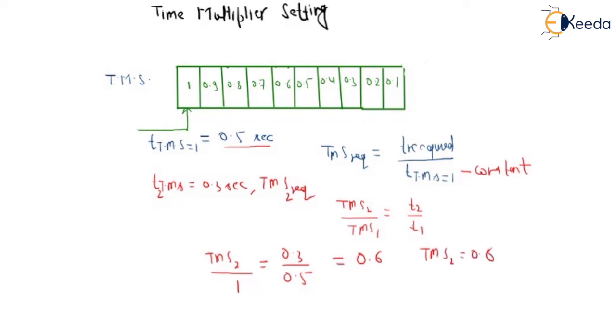If we want to operate our relay at 0.3 seconds, then we should have set this to 0.6. Means we have to change this time multiplier setting to 0.6, so it will operate in 0.3 seconds. So this is how we will have the idea of time multiplier setting.